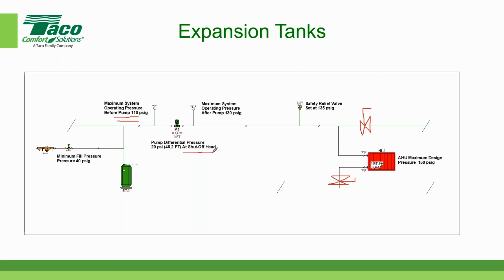So in other words, at zero flow, there's no place for the water to flow in my little example here. So the maximum pressure that the pump could produce is the shutoff head, and that's at 0 gallons per minute. And in this case, I happened to look up a pump that had a 20 PSI differential pressure at zero flow. So that's where I came up with that value. Very important. That's not an arbitrary number. That is a findable number from the pump curves.